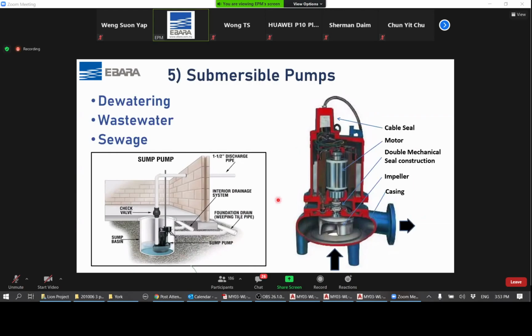If you look at the construction of a typical submersible pump, you will see here a picture of a cutout. Usually the suction will come from the bottom, and this is the pump casing, the volute casing, and the impeller will be taking suction from the bottom and discharging it to the side. And you have the motor. This submersible pump will be using what we call a submersible motor, and this is housed in its casing.